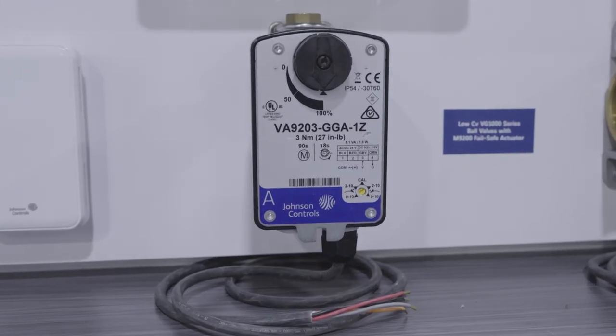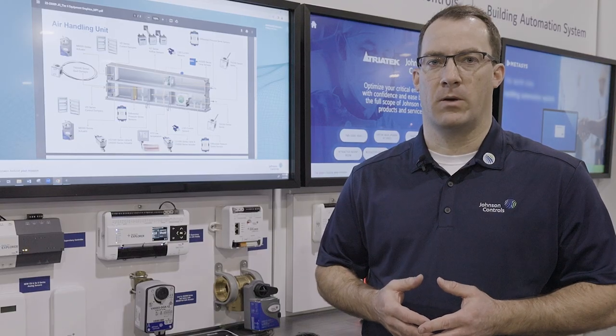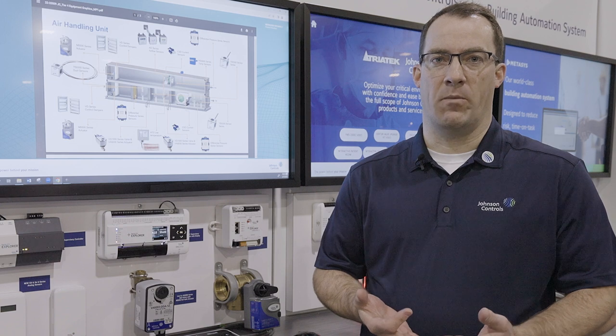Here we have our VG-1000 Low CV ball valve with a M9200 series actuator. The Low CV ball valve is a new innovation from Johnson Controls. We've lowered the minimum CV from 1.2 down to 0.3 to reduce maximum flow, improve controllability, and improve energy efficiency in the equipment it's used with.